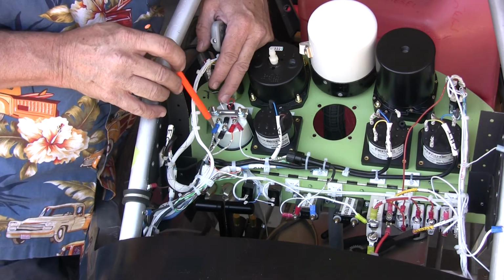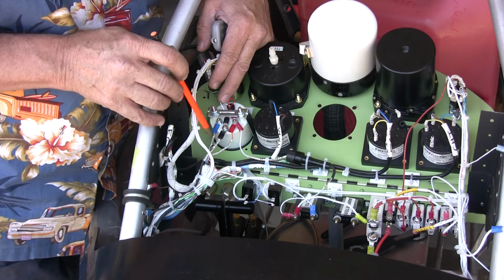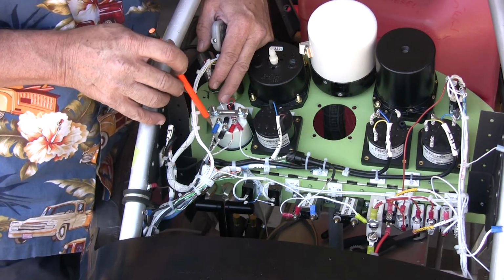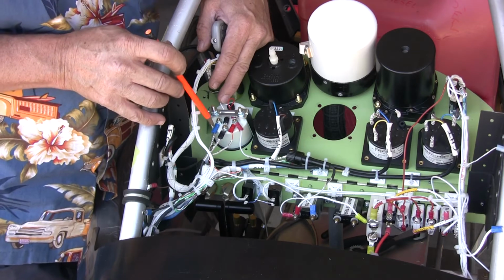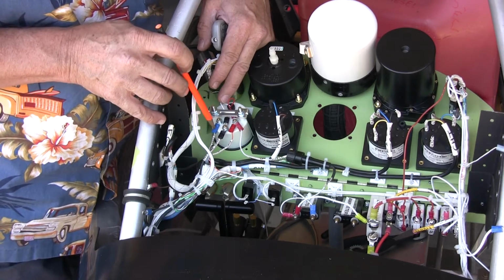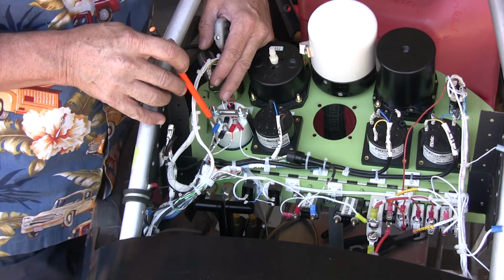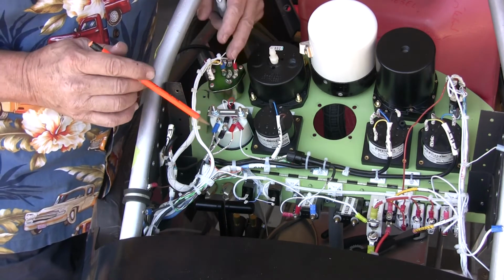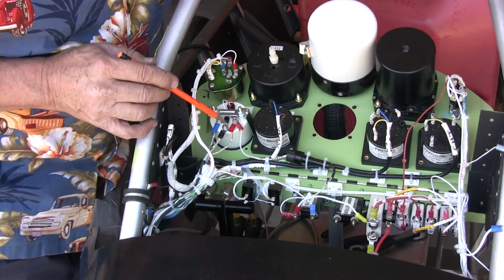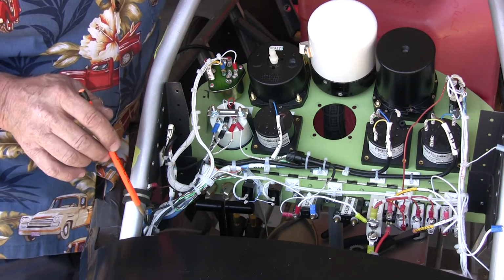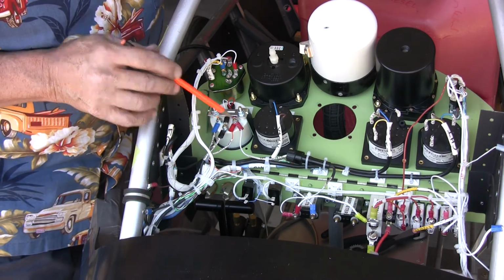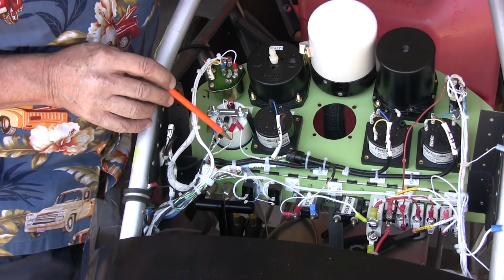Over here is the blue connector, which is from the fuel probe sending unit. This is marked S on the gauge, and it carries the signal from the sender, the capacitance probe. I have a ground that goes from the center here out to airframe ground, and then a wire coming up from the fuel probe.